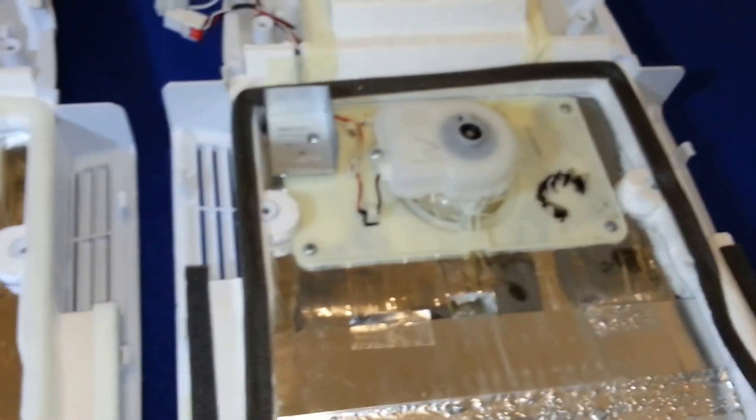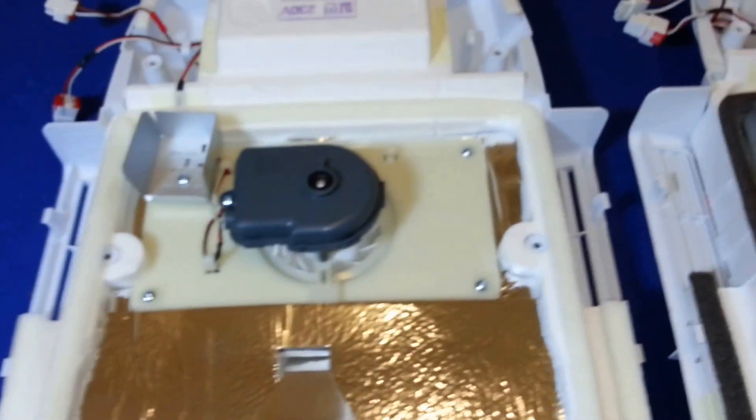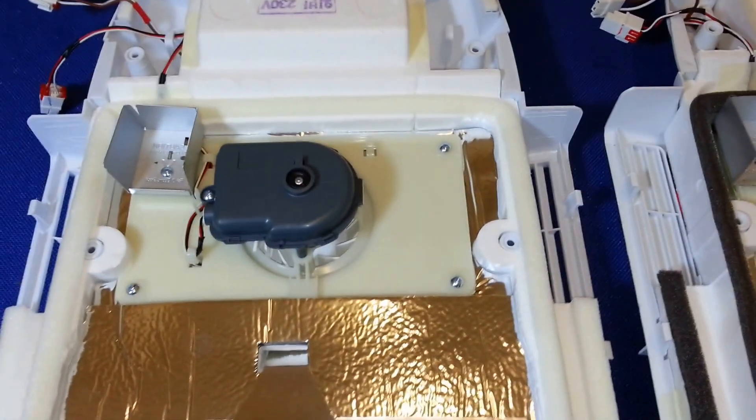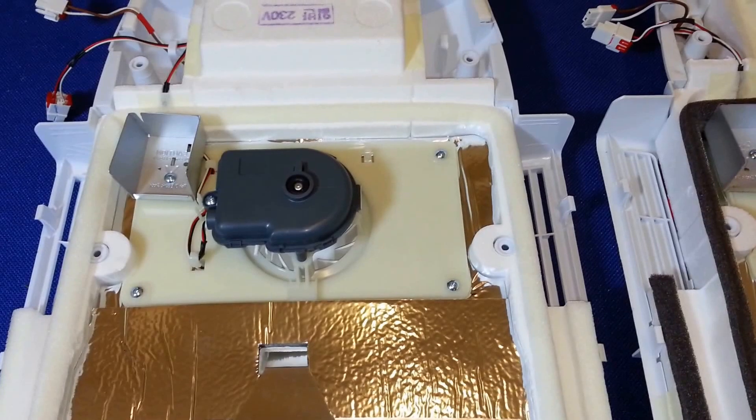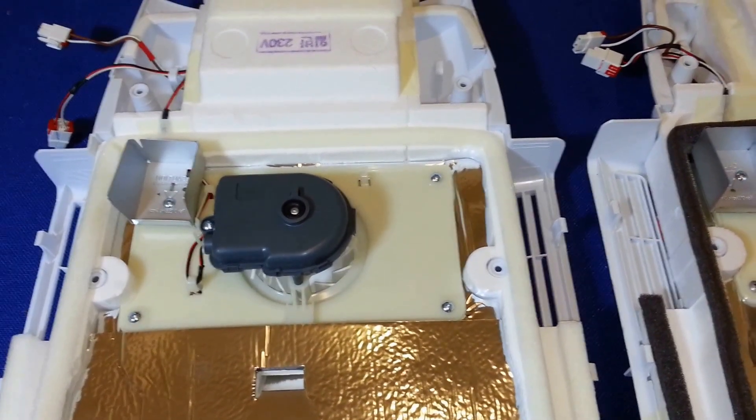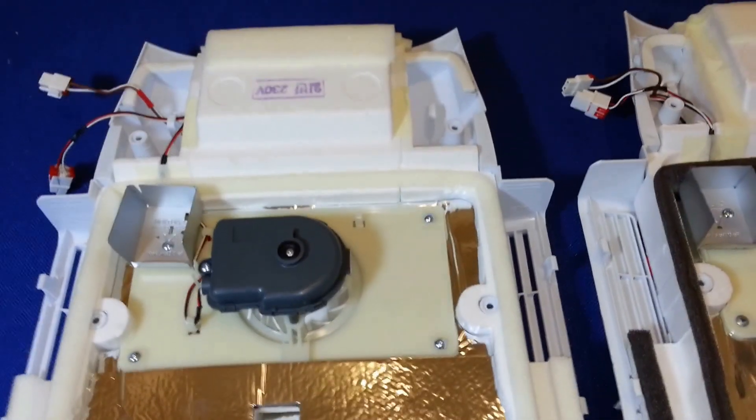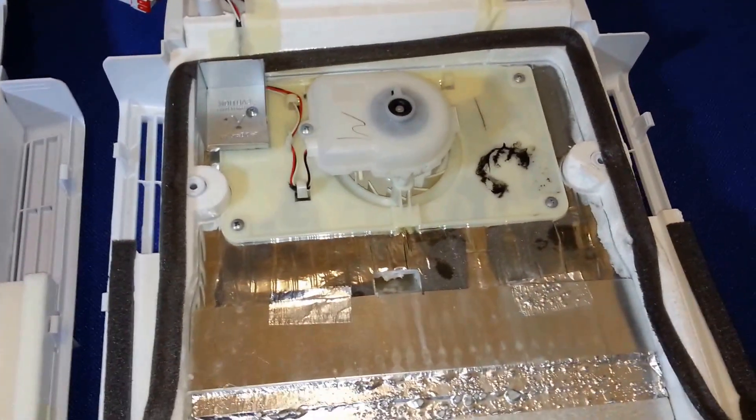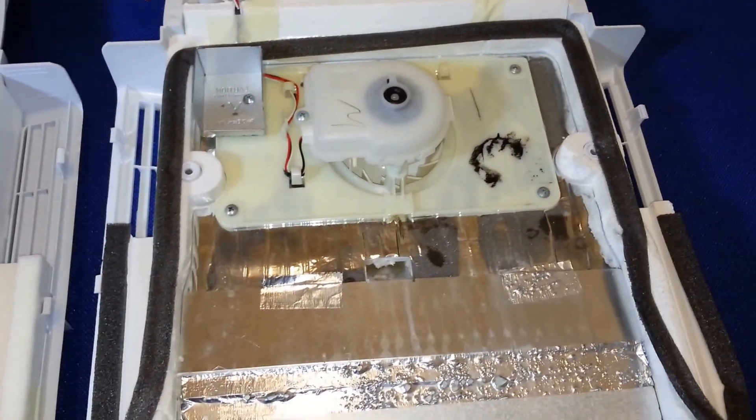Just a point on the fans: we've got a lot of customers phoning up wanting to purchase a fan as they think their fan's gone faulty, it's making a noise. Basically the fan's only making a noise because there's ice hitting it. If you defrost it all, the noise will go away.